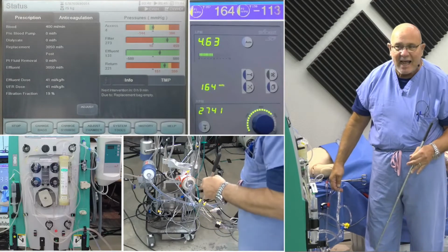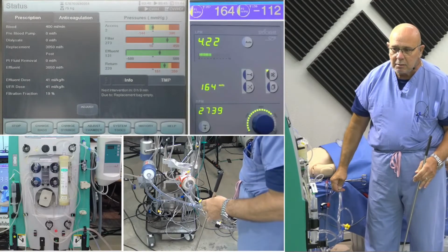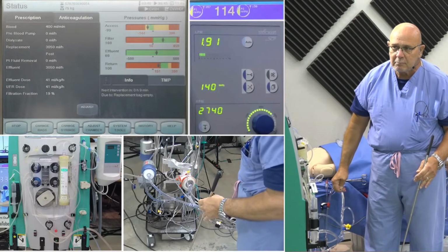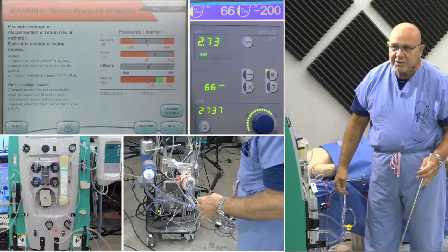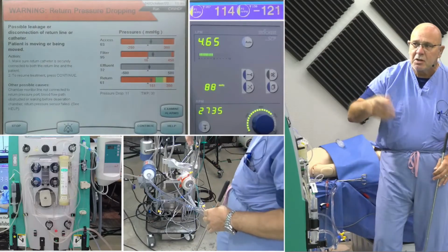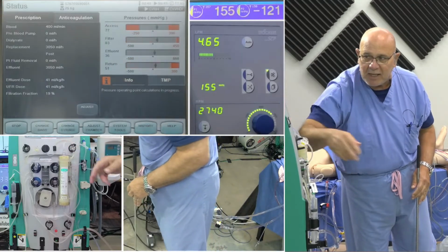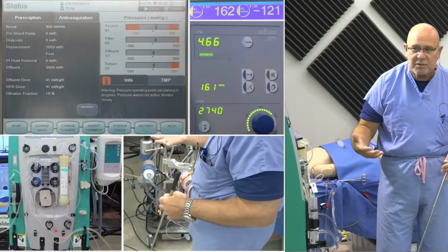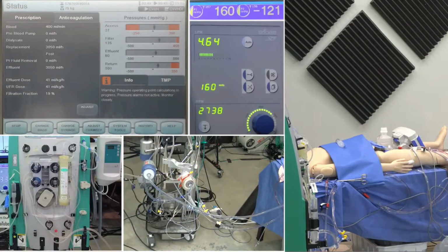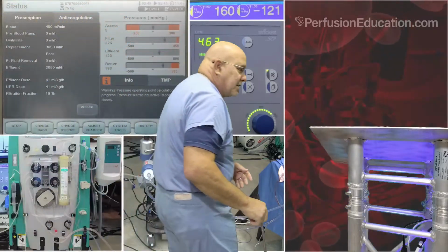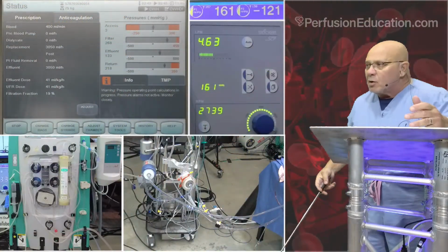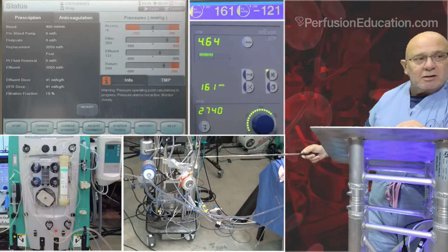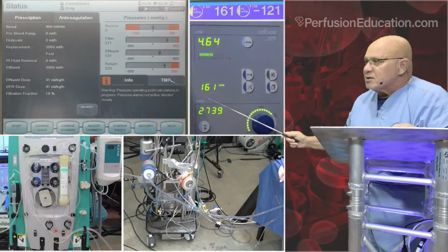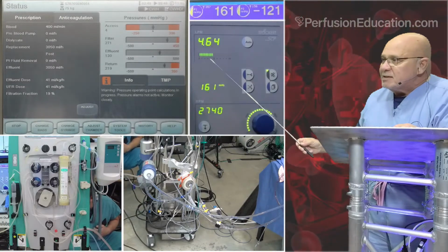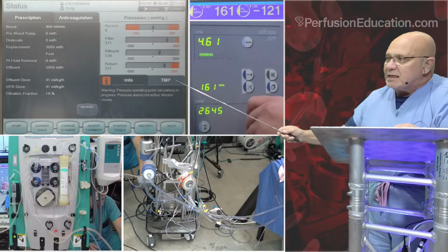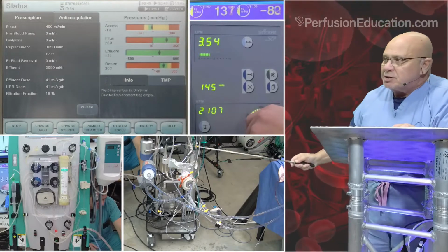So I'll give you an example. I'll just act as if we were having chatter. And you see, just by doing that enough times, we finally got return pressure dropping. So it's very sensitive and it sees all of those kinds of things. Okay. All right, so with all of that said, and of course there's limitations, Magic, if you want to just do this, if you're going to be messing around with it and going up on the flow and down on the flow, so the flow on the ECMO, and you can just vacillate it, let's say take it down to 3 liters, and you'll immediately see these numbers all change.